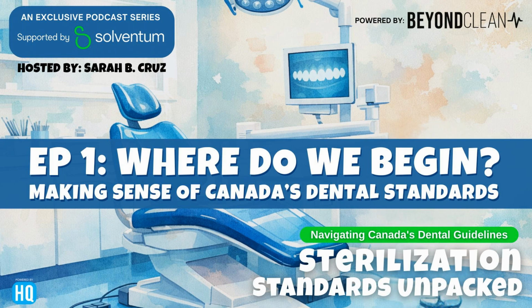So in Quebec, they're integrating the CSA Z314 and Health Canada language in 2022. And the Health Canada language came out in 2020, where they provide the federal foundation for medical device classifications, licensing, and reuse validation. They're including the Spaulding classification system. They're requiring validated manufacturing IFUs for reusable instruments. And they're going to ensure that imported and domestic devices meet labeling, safety, and performance standards. So that's in Quebec, right?